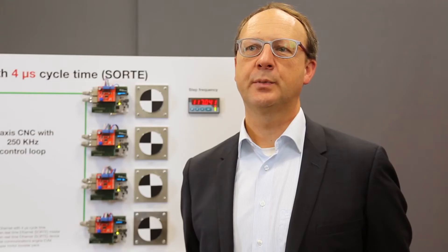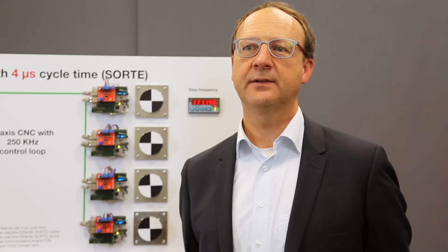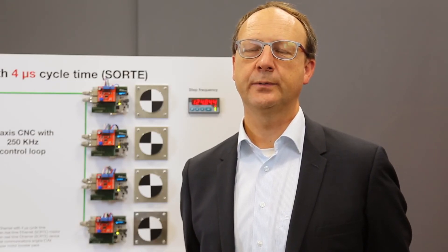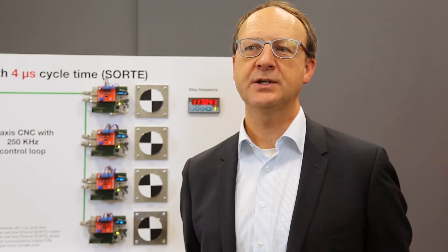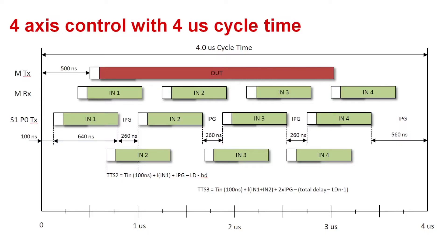The four microsecond cycle time for four axes is supported by TI industrial Ethernet and Sitara processors with integrated industrial communication IP. There is one multicast packet to all four devices which contains 16 bytes of output data, and each device sends back 8 bytes of input and diagnostic data to the master.